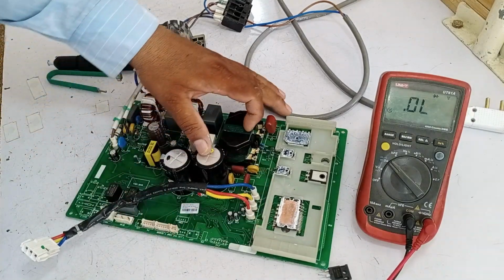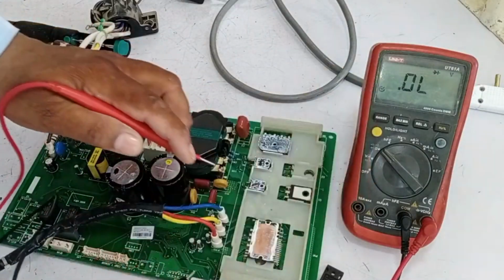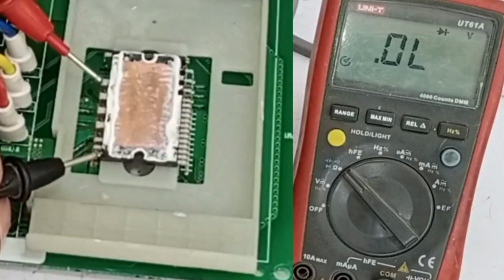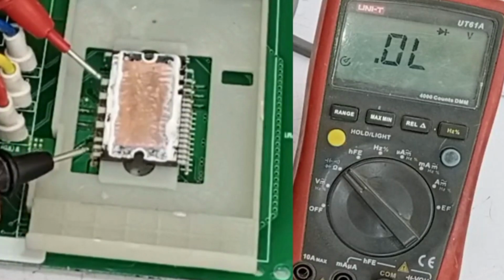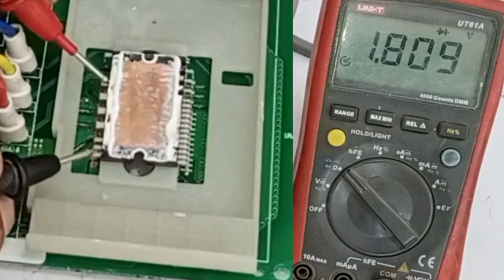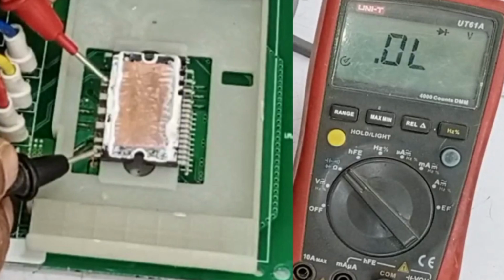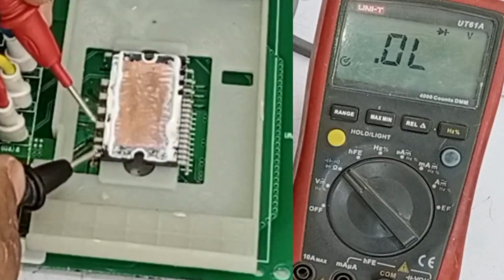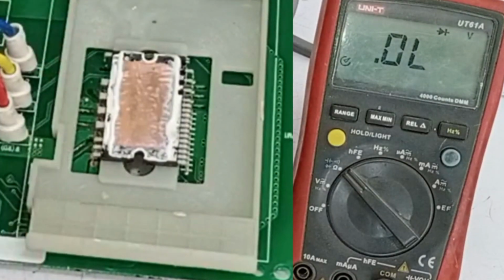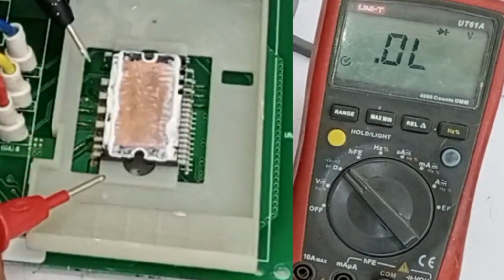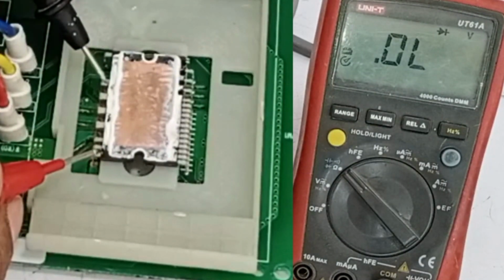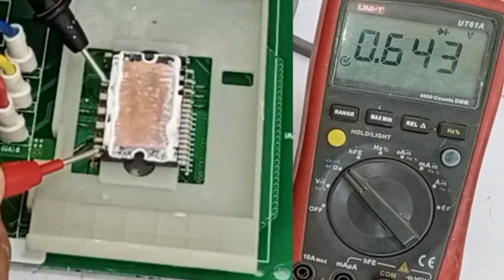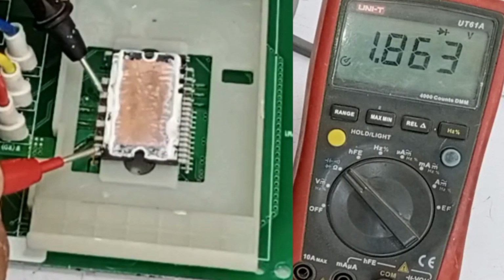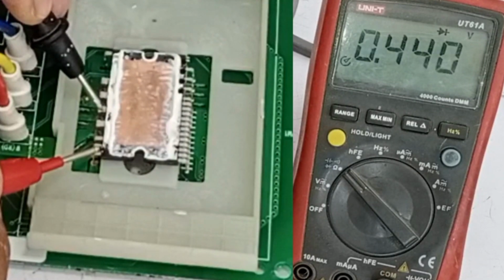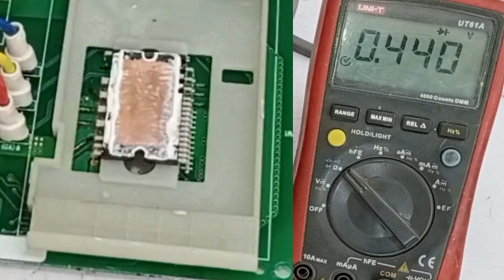Let's see if things have improved. I've set the multimeter to diode mode. Now, when I test the IPM by placing the positive probe on the positive and the negative on the negative, we'll see what value it shows. If the value initially goes high and then drops, it means that one side is working fine. Now let's reverse the polarity, placing the positive probe on the negative and the negative probe on the positive. Here, it's giving a reading of 0.643, whereas before the value was higher, which is a good sign. This means that our IPM is completely fine and there's no issue with it.